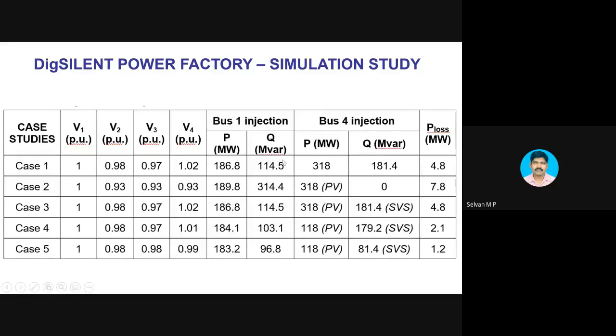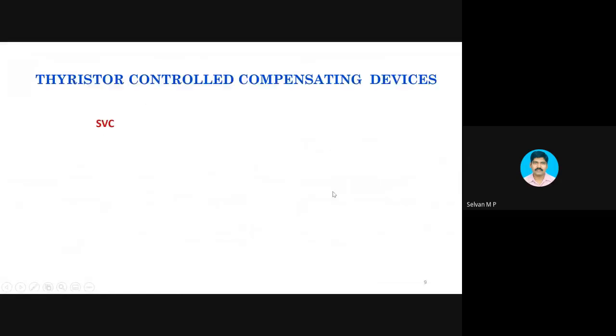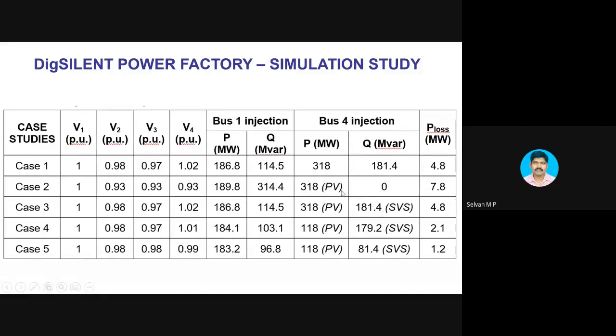From this we can find out 186 plus 318, so it becomes around 500 megawatt is the demand. Say there is 5 megawatt loss. So 500 megawatt load is available in this system. So I am worried about supplying only that 500 megawatt load. So I want to concentrate on renewable. I want to go for PV system. I throw the synchronous machine out and I connect a PV system for 318 megawatt.